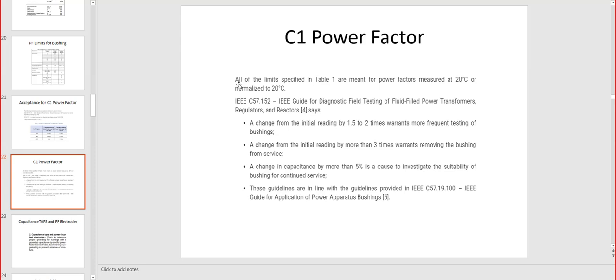C1 power factor, so all the limits in table 1 are meant for power factor measured at 20 degrees C, normalized to 20, and change from the initial reading by 1.5 to 2 times. So if a change happens in that ratio, 1.5 to 2 times, it warrants more frequent testing. If the change happens more than 3 times, then remove the bushing from service. So it's not just the limit, it is the variation of the reading. A change of capacitance by more than 5% is a cause to investigate the bushing. These guidelines are in line with the IEEE guideline for apparatus bushing. So that's the standard from where this variation in reading is taken.